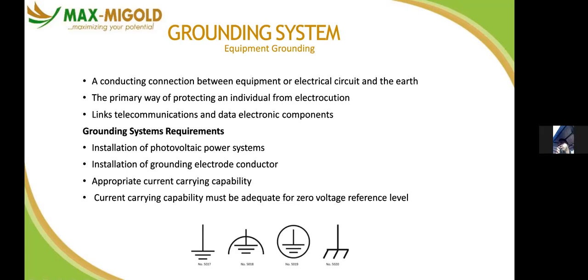Sorry, there's a value you called. Yeah, I said the earth resistance must not exceed 5 ohms. Ohms, 5 ohms, that's the unit of resistance. It must not exceed. If you have more than 5 ohms, the resistance is so much that the electricity will not flow, and you request for improvement of your earthing arrangement. That means your earthing system is compromised. It's not healthy. But 5 ohms is even too much.